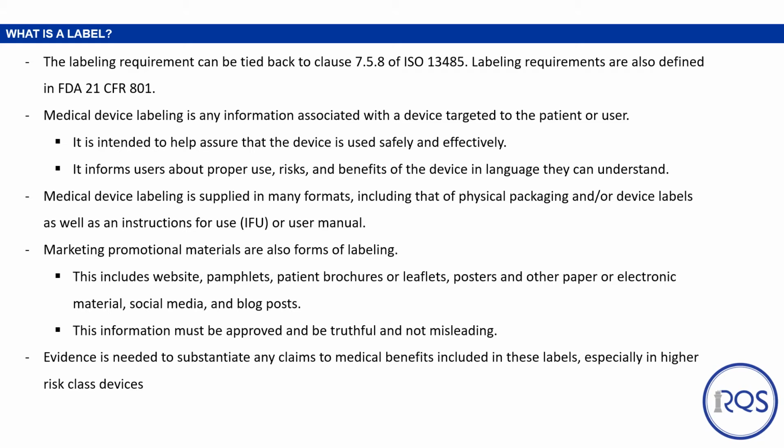Marketing promotional materials are also forms of labeling. This includes websites, pamphlets, patient brochures, posters, social media posts, blog posts, etc. This information must be approved and be truthful and not misleading. Evidence is needed to substantiate any claims to medical benefits in these labels, especially for higher risk devices.